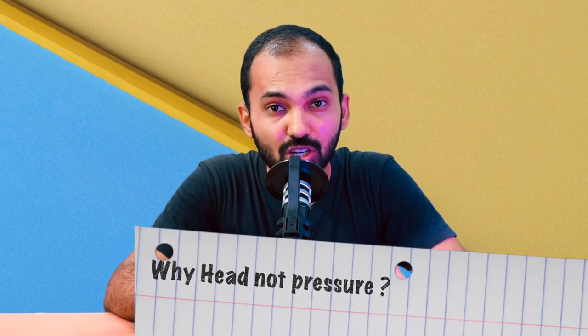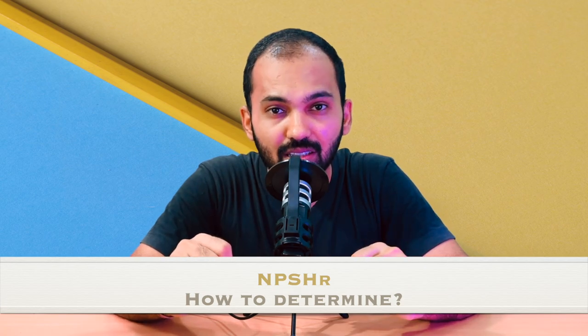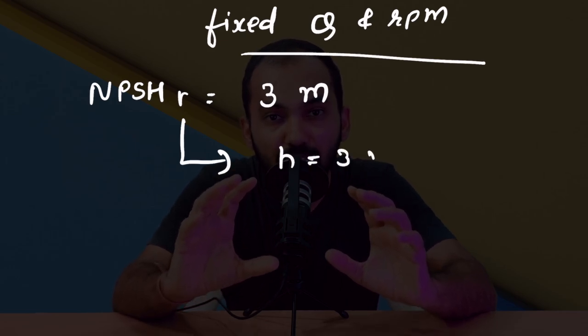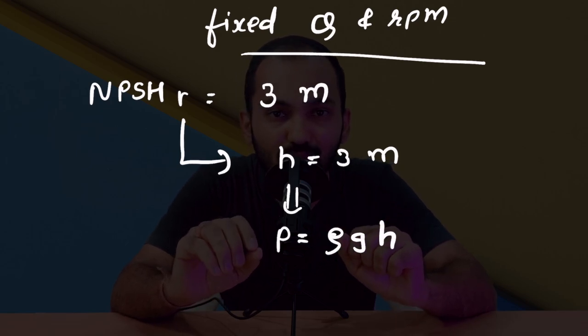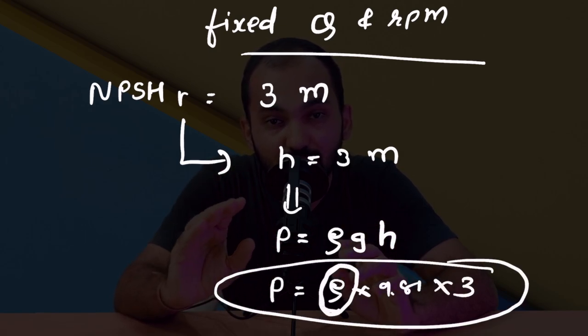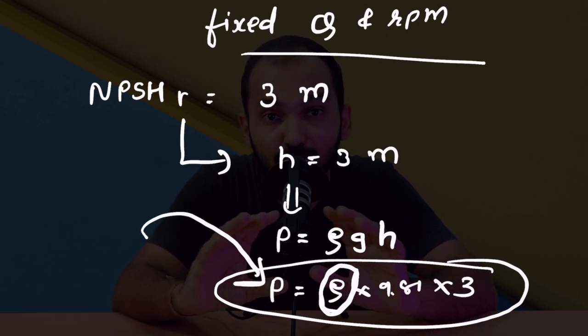Two values are important: first, NPSH available calculated at given conditions, and second, NPSH required provided by the pump manufacturer. Two questions arise: why does the pump manufacturer give NPSH in terms of head rather than pressure? And how does the pump manufacturer decide NPSH required? The reason head is used is that pump manufacturers test NPSH required using water as the reference fluid and determine the limits. For a certain flow rate and RPM, if NPSH required is 3 meters, then for a different fluid we use p = ρgh — multiplying by that fluid's density gives a different limiting pressure, but the head value of 3 meters remains the same.